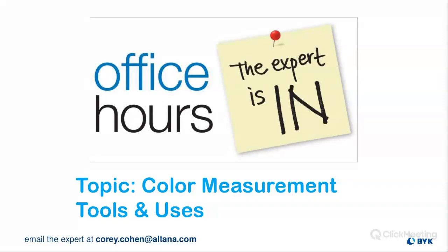And then we have the Smart Lab side, which is very versatile in the various things you can do with it. You can take a color measurement, and once that data is in the software, you can really play with it any way you want. Even if it was measured under one condition, you can change the settings, and it will automatically recalculate the data so that you can see it under different illuminants.